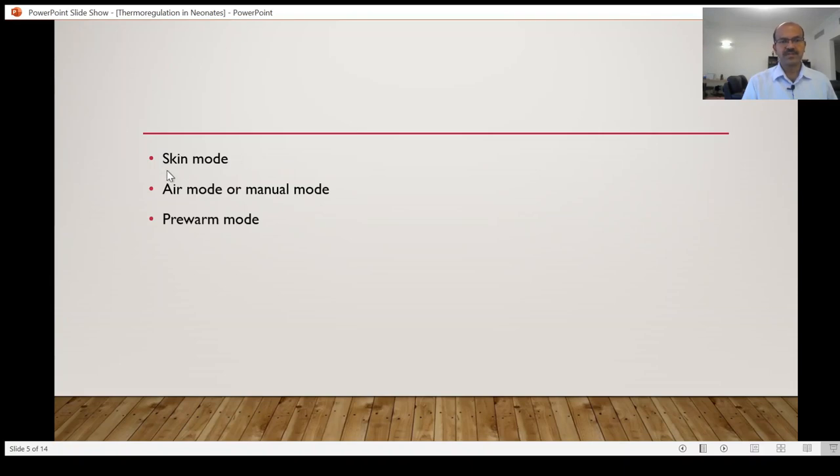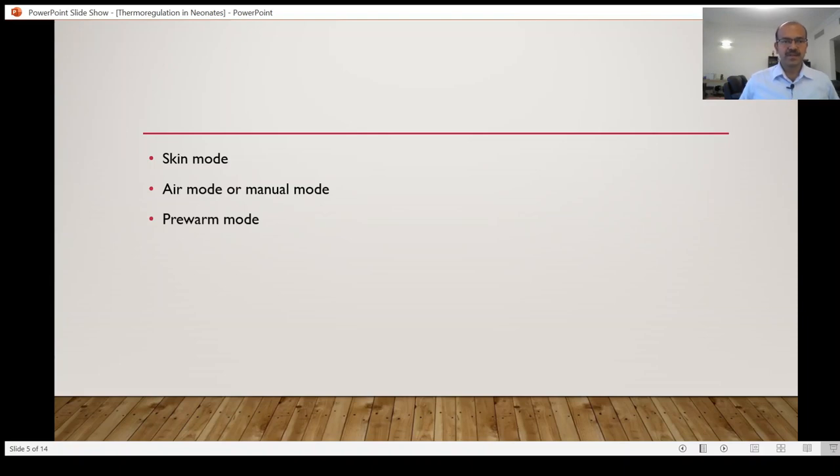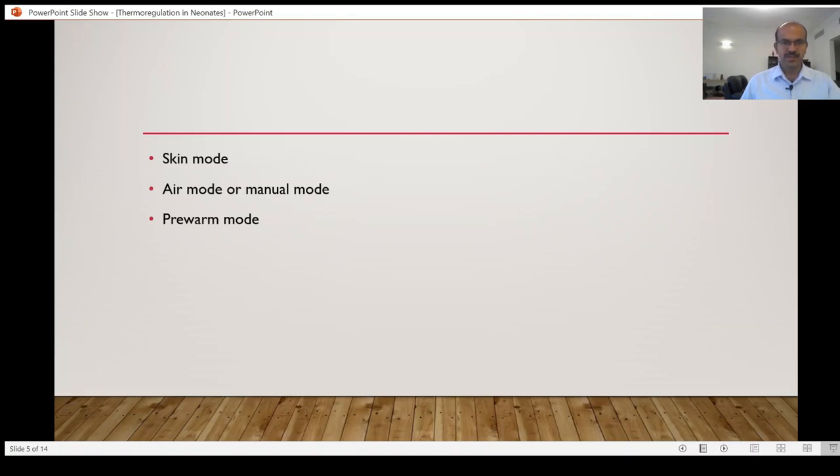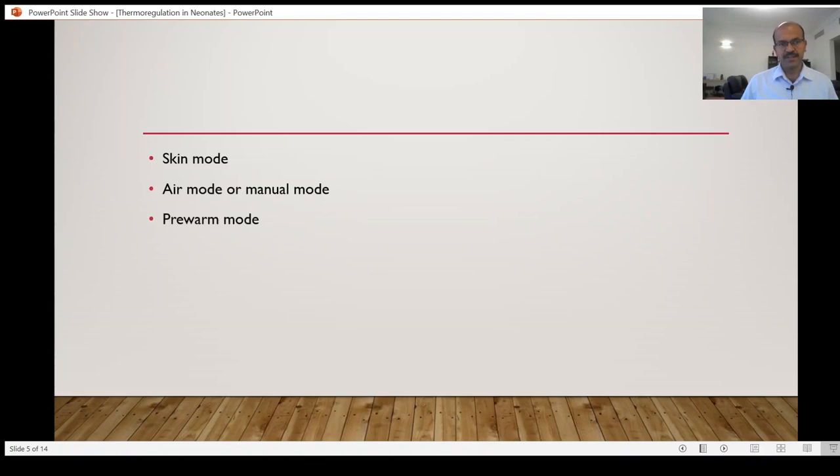So we have three main modes on the open care system. We have the skin mode, so this can be used soon after admission for monitoring a baby. Suppose a baby has a brief transient tachypnea of newborn, you expect the baby to settle down within a few hours after the delivery and you plan to shift. It's easier to clean the open care system and it's a term baby, so there is no harm in receiving the baby and keeping them on the skin mode in the beginning because the temperature is labile soon after delivery.